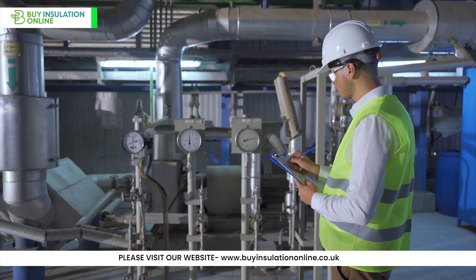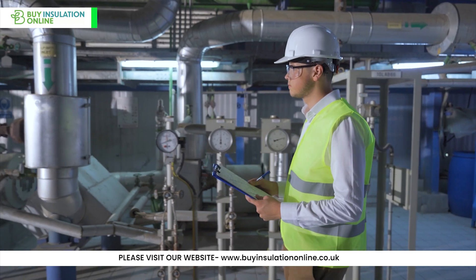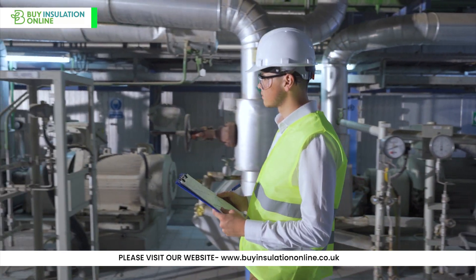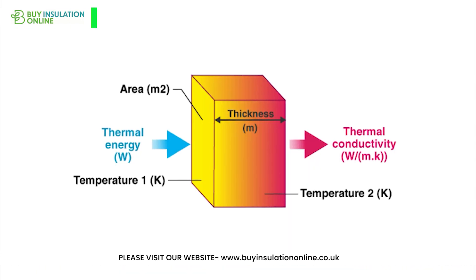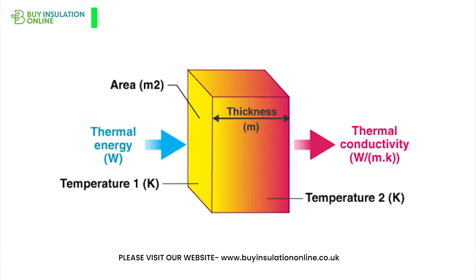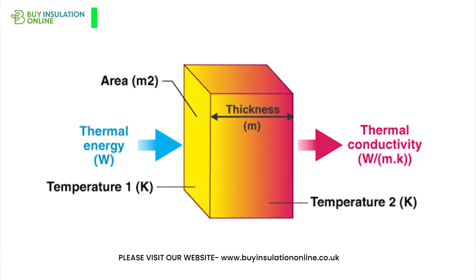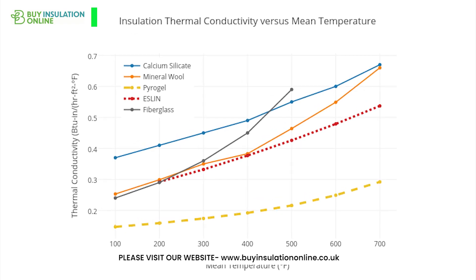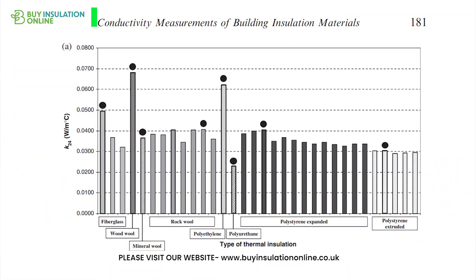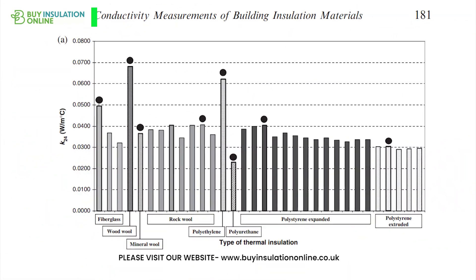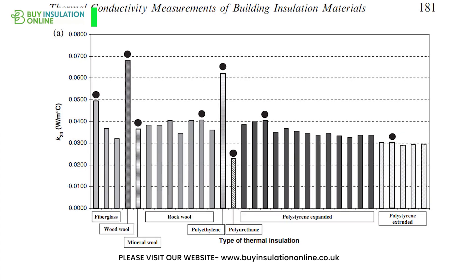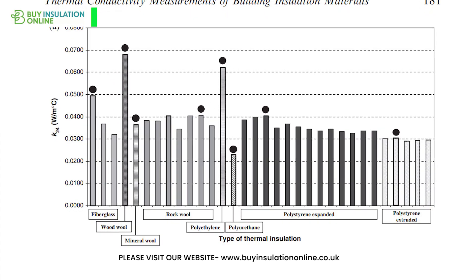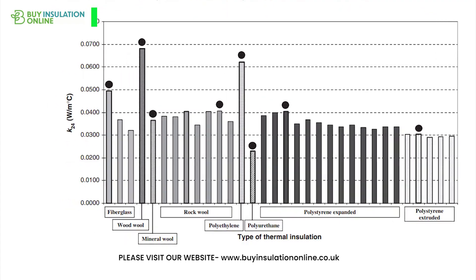When determining the right pipe insulation thickness for a project, several factors must be taken into account. The thermal conductivity of the insulation is known as the lambda or the k value, and is expressed in watts per metre kelvin. The k value is a measure of the thermal conductivity of an insulation material — it is a ratio of the rate of heat transfer through the material to the temperature difference on either side of it. The lower the k value, the better the insulation material is at preventing heat transfer.